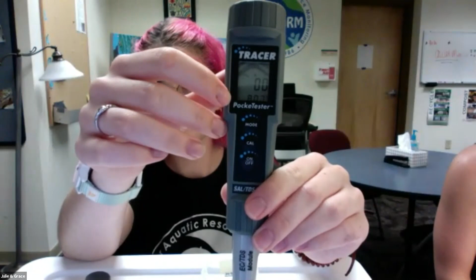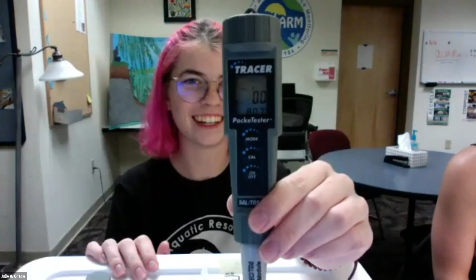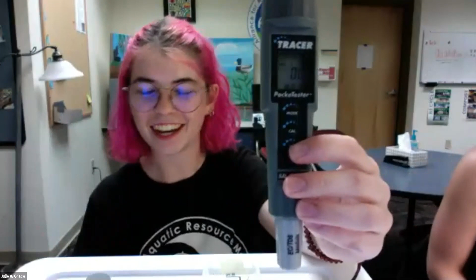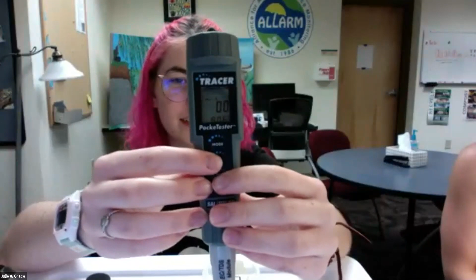Now you're ready to remove your electrode cap and turn the meter on, pressing the on-off button as we said earlier. This would also be an excellent time to check the bottom right corner on the meter and make sure that you are in degrees Celsius. Is anybody not in Celsius? Grace is not. So this will be great for us to show you if you are not. All right, so we'll go over quickly turning it into degrees Celsius if anybody needs to go over that quickly.